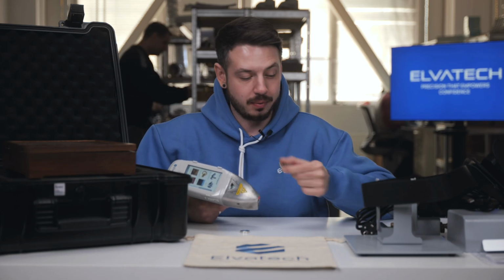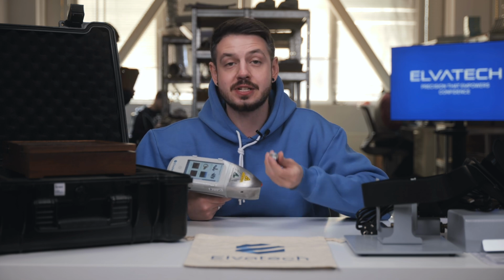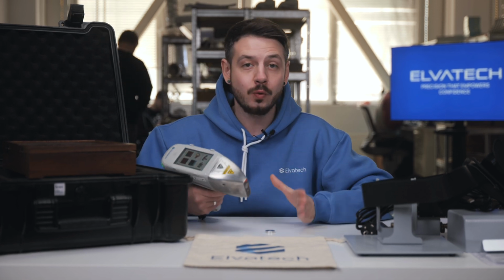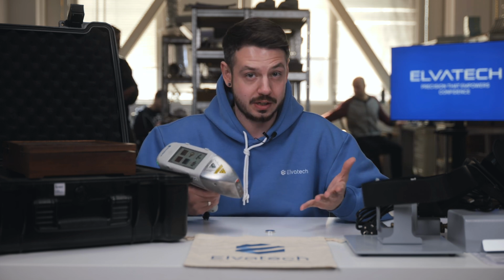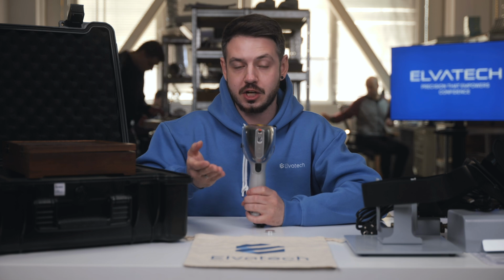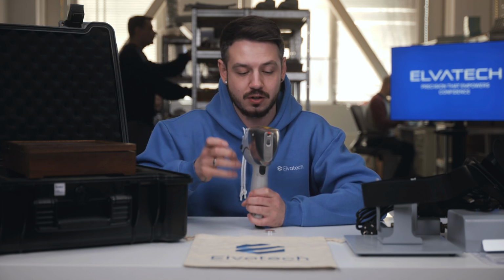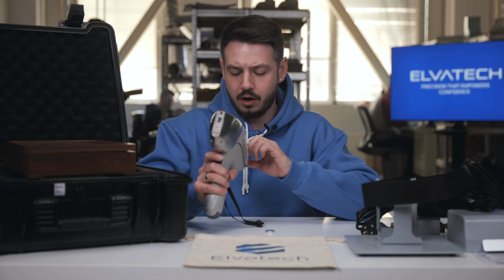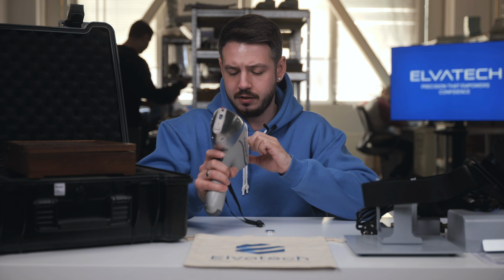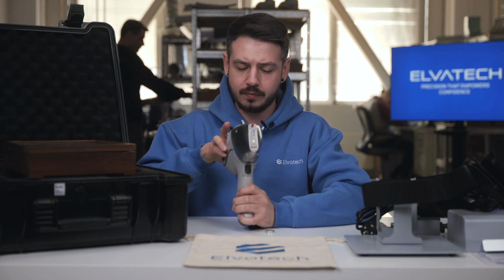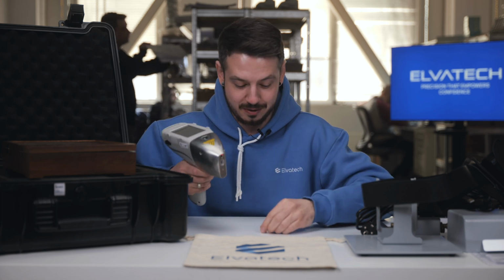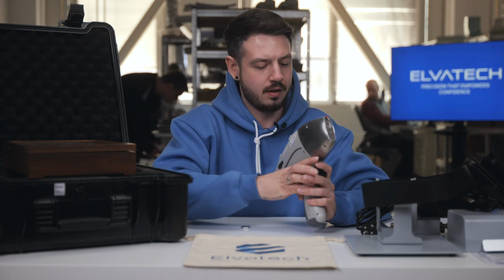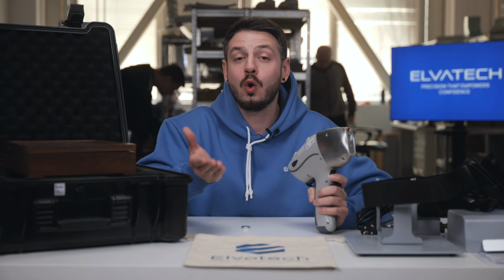We move our previous sample on a side, and now let's measure our 7075 sample. And actually, we know that this one contains some of the light elements, mostly. So all we need to do is switch calibration, and set alloys with light elements option. This device is actually ProSpector 2LE, so it has the integrated option for light elements measuring. Right, just checking the settings for the duration, as we need it for 5 seconds. Alright, accept it, and now we can measure. All measuring of light elements always going in 2 passes. And let's check the result here.